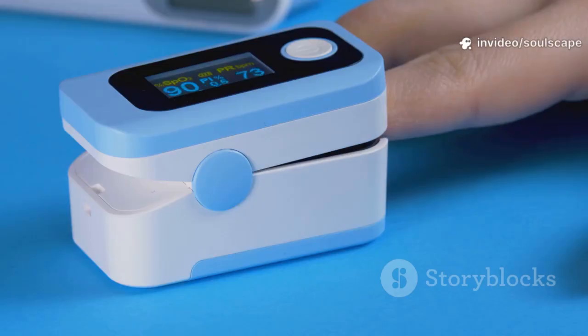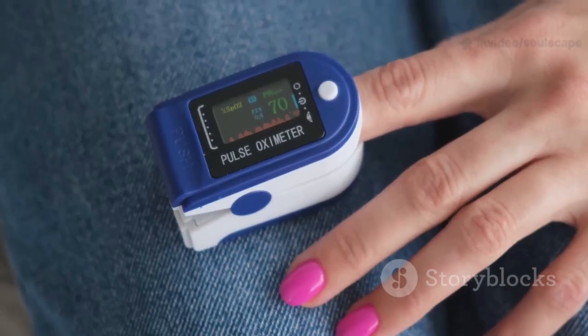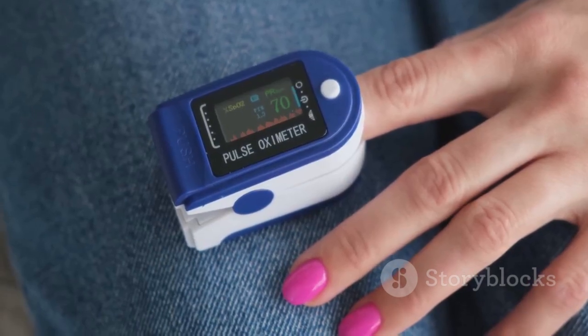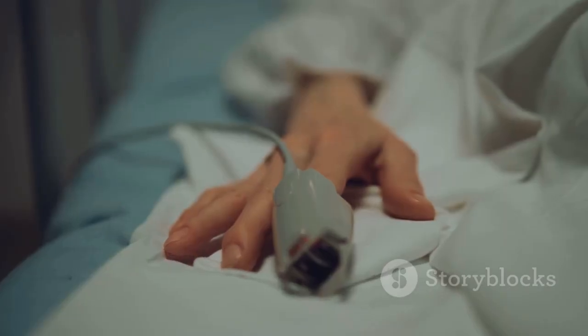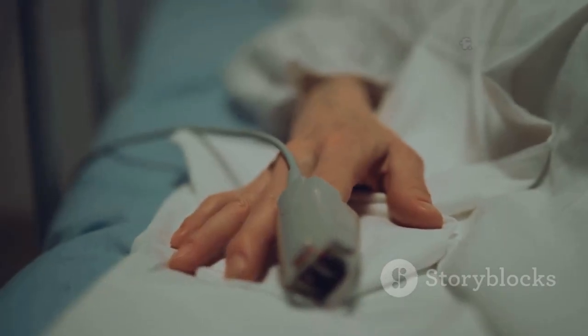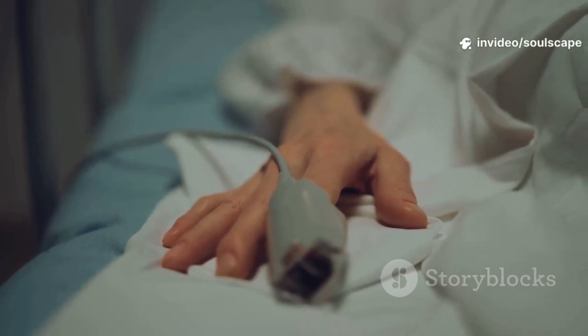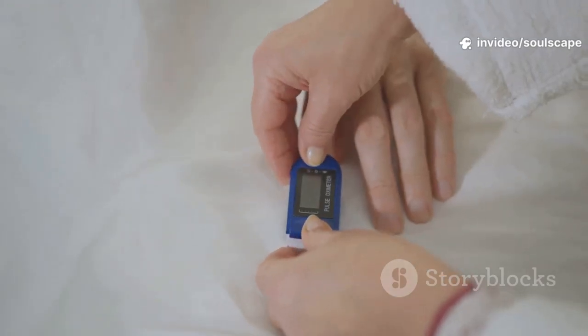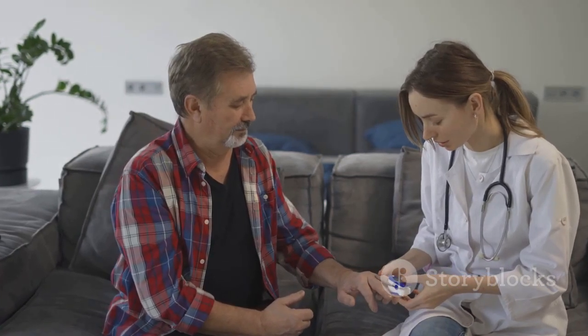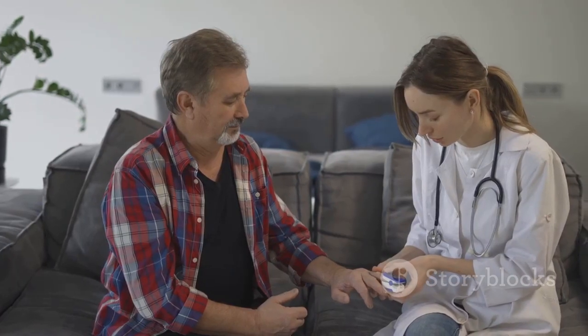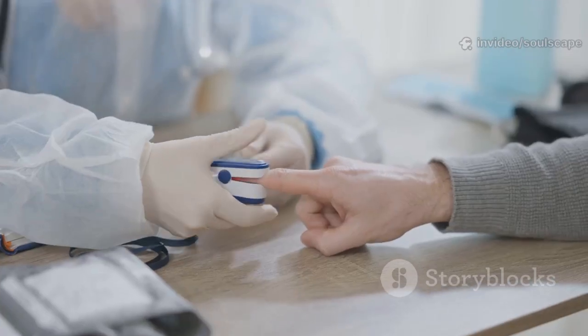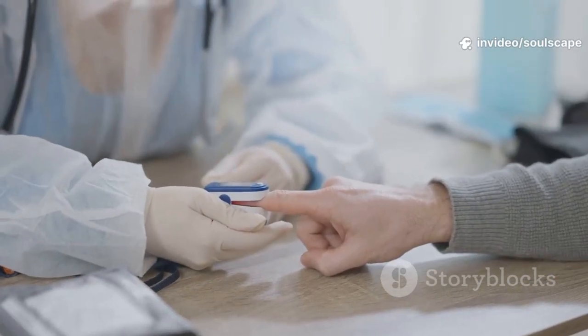Accuracy? Pulse oximeters are pretty reliable for oxygen saturations between 70 and 100%. But, and this is a big but, there are times when you can get a false reading. For example, if the patient is in hypovolemic shock and there's not enough blood flow to the finger, or if they're wearing blue or green nail polish. Carbon monoxide poisoning also messes with the readings, since the device can't tell the difference between oxyhemoglobin and carboxyhemoglobin. And if there are certain dyes in the blood, you might get the wrong results.